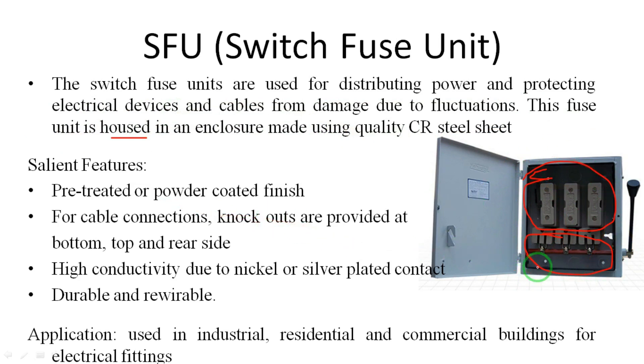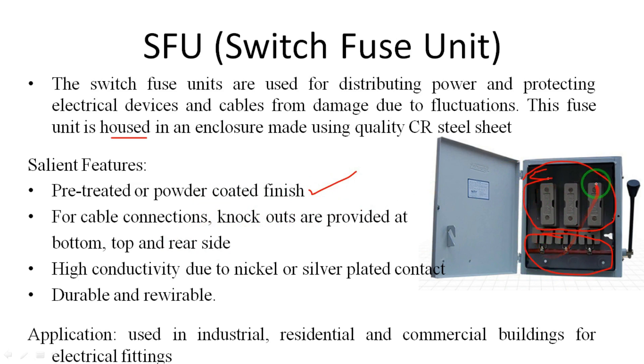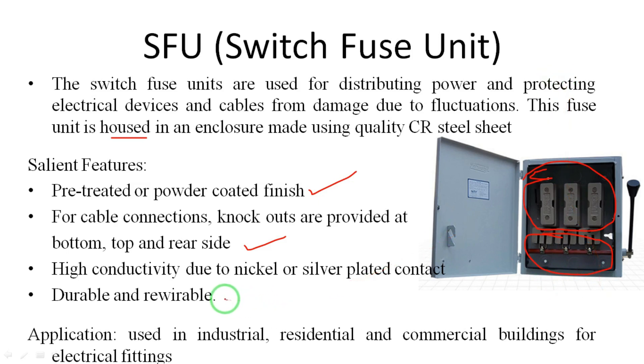The main features of a switch fuse unit are: it has a pre-treated or powder-coated finish; knockouts are provided at the bottom, top, and rear for cable connections, allowing cables to enter and leave; and it has high conductivity due to nickel or silver-plated core contacts, meaning the switching contacts are made from silver or nickel material for the purpose of high conductivity.